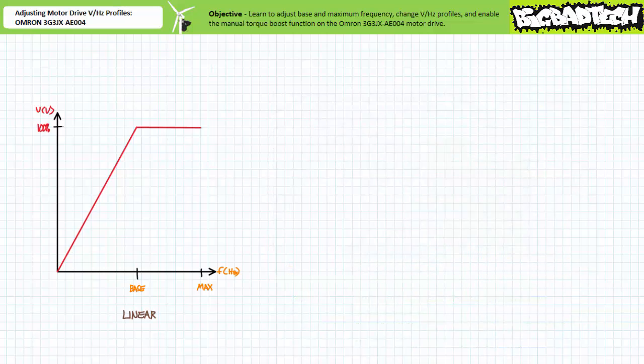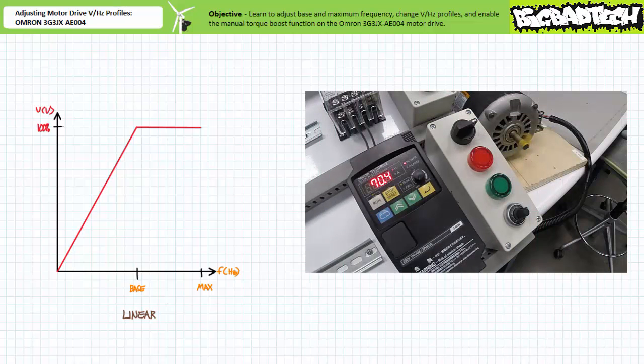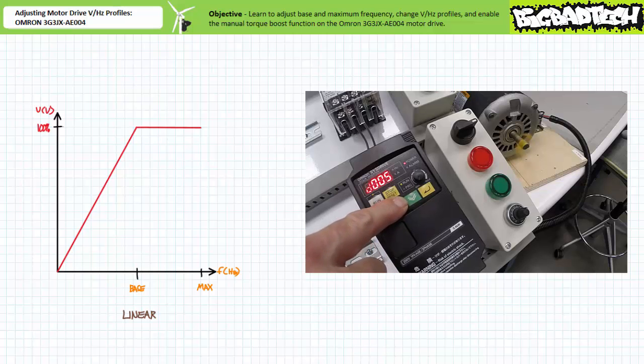We can perform the same inspection at various points inside the 0 to 100 hertz excitation frequency range to find linearly increasing applied voltage up to the base frequency of 60 hertz, beyond which applied voltage flat lines at 100 percent. For example, at an excitation frequency of 70 hertz, we find parameter D013 output voltage monitor to be roughly 100 percent of the available line-to-line voltage.